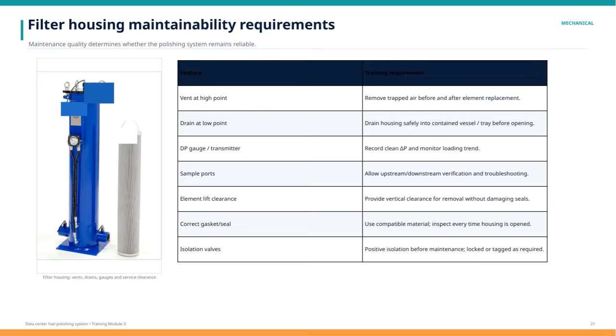The differential pressure gauge or transmitter plays a key role by allowing us to record the clean differential pressure and monitor the loading trend, which helps in deciding when service is needed. Sample ports provide the ability to verify conditions upstream and downstream, which is vital for troubleshooting any issues quickly. When removing filter elements, it's essential to have sufficient vertical clearance to avoid damaging seals. Additionally, ensuring the correct gasket or seal material is used and inspecting it each time the housing is opened helps maintain a proper seal and prevents leaks.